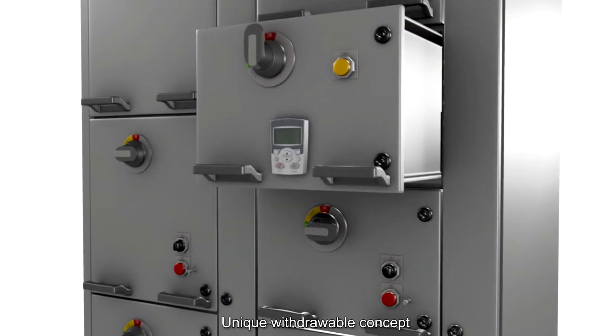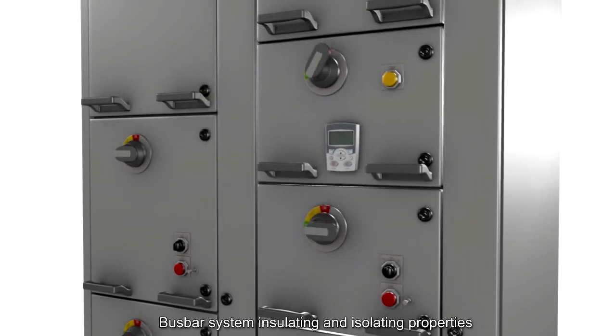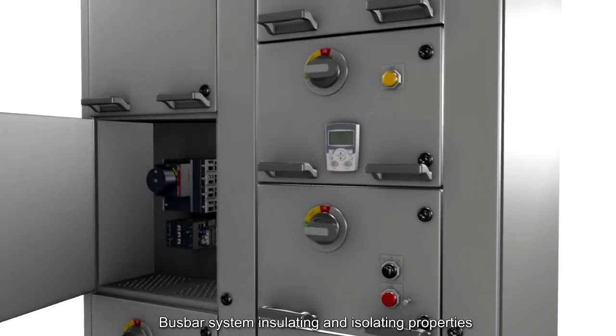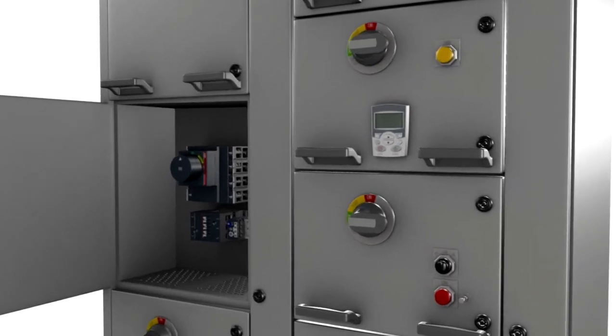The entirely unique withdrawable concept incorporated in the MNS MCC allows an operator to safely withdraw a unit without opening any doors, using any tools, or disturbing any field wiring. The insulating and isolating properties of the busbar system and the withdrawable unit concept substantially eliminates the risk of an operator coming into contact with an energized part.